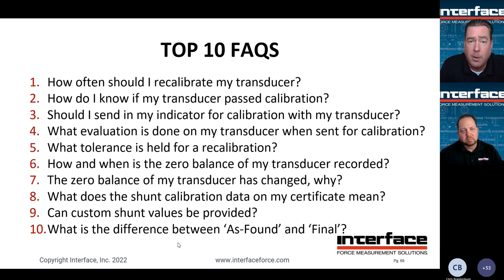How and when is the zero balance of my transducer recorded? This is another pretty common question. If it's a tension and compression load cell, typically speaking, we perform the compression calibration first, followed by the tension calibration, and the zero balance is recorded as the final step when the load cell comes out of the calibration frame. Obviously, if it's a compression only load cell, only one direction there, so it would be recorded after that compression run.